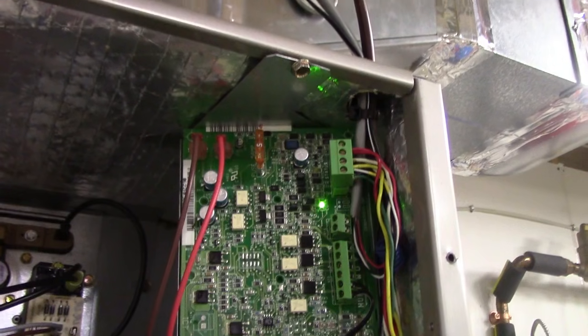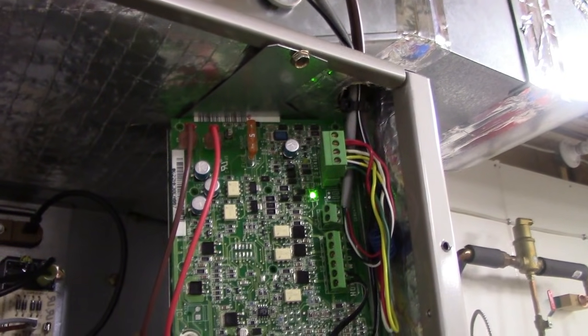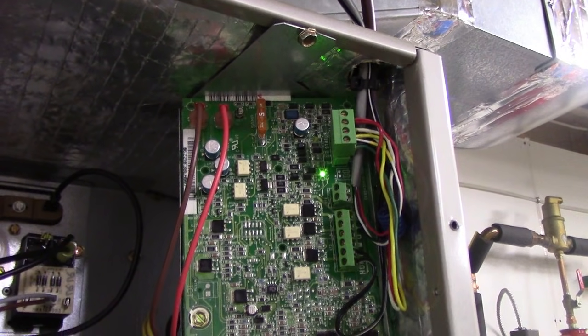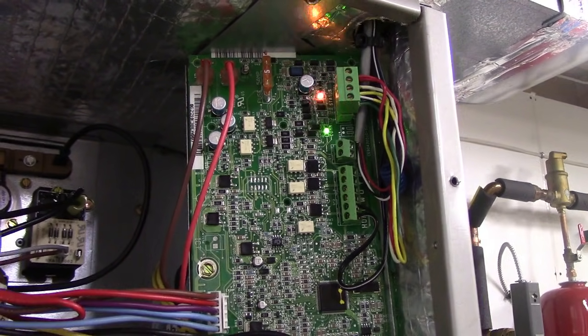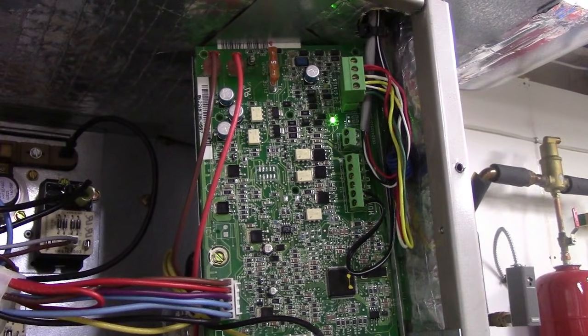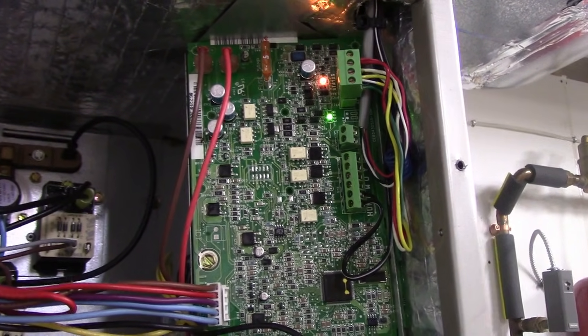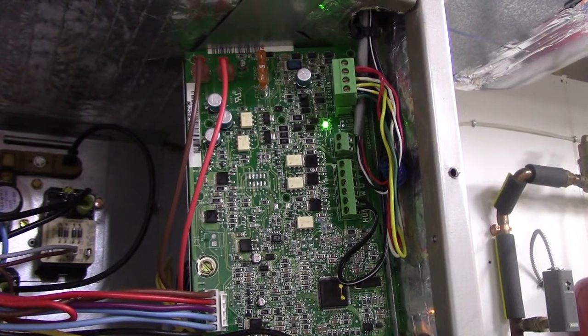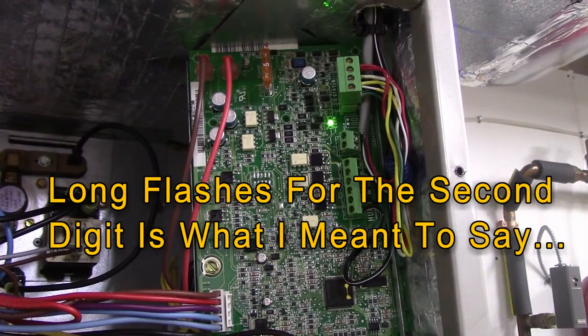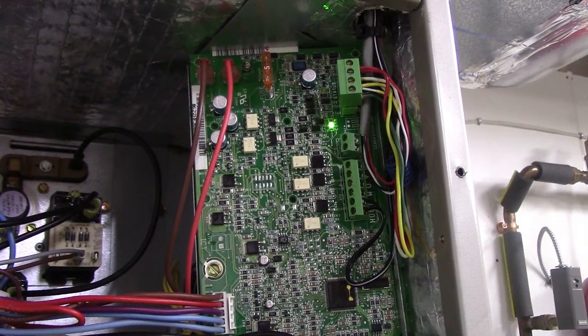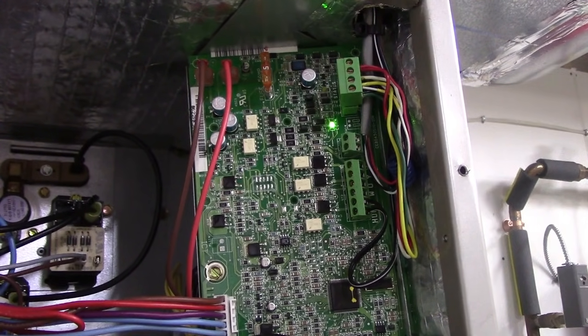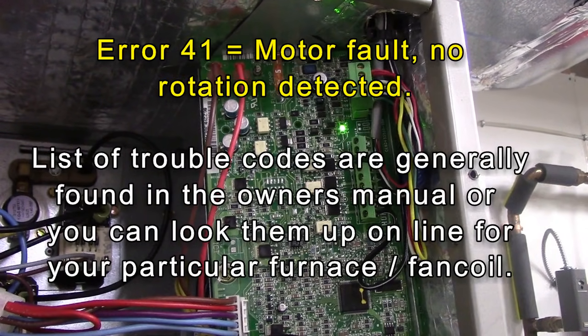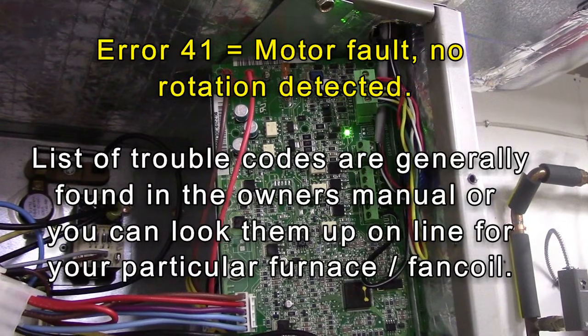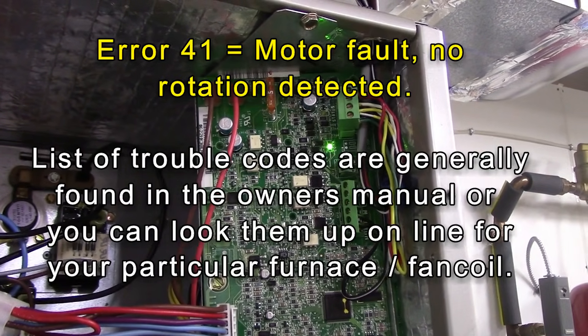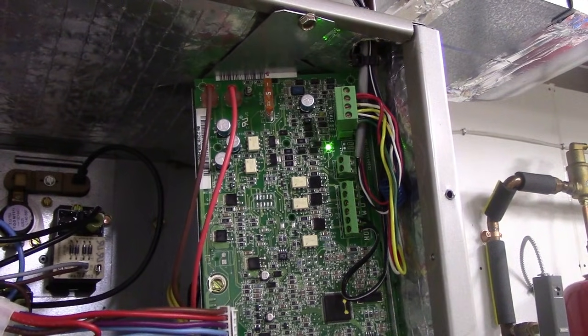And then if we actually go up to our control board, if you don't have a communicating thermostat, you can also read fault codes on most modern new furnaces or fan coils. Right on the motherboard there'll be a status LED, and it will indicate codes. In this particular one, it gives short flashes for the first digit of the code, long flashes for the second. I'll just wait till it starts cycling again. 1, 2, 3, 4, 1. So error code 41, just like we saw up at the thermostat. So again, if you don't have a communicating thermostat, that's the other way you diagnose these: on the control board you'd read off the fault code that's flashing.